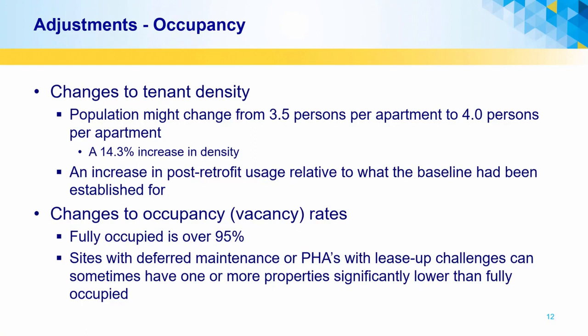Fewer people and fewer occupied apartments will directly result in apparent savings, that is, usage reduction, that are not related to conservation measures. Usage such as lighting will go down if an apartment is empty, since lighting will be turned off by property management. Heat or air conditioning may also be reduced if the apartments have individual controls. Central plants serving large control zones won't perform much differently for the loss of individual apartments.